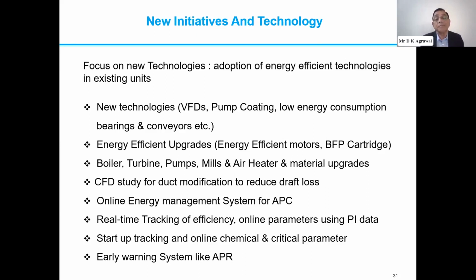There are cases where I've seen people increase the height of the air preheater baskets, or change the profile of the baskets, and benefit from that. CFD study is also something many people have adopted in the draft systems, and many times you find that unequal flows are there. Even the recurring problem of duct leakages, attended to during overhauls, can be taken care of by making a CFD study, and deflectors, diverters and all those things can be installed.